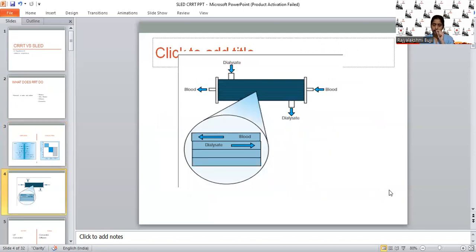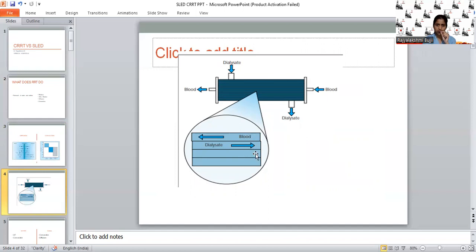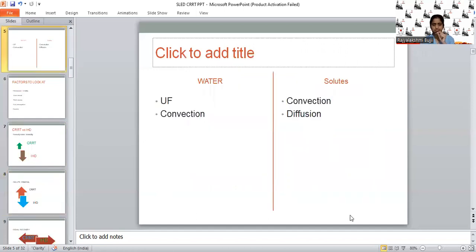In the case of intermittent hemodialysis, the diffusion process is facilitated by counter-current flow of both blood and dialysate fluid. The filter contains parallelly placed porous channels; within the channels, blood will circulate, and around the channels, dialysate fluid will circulate — but both move in opposite directions. This facilitates the concentration gradient and diffusion process. Water will get removed with the help of filtration and convection; solutes will get removed with convection and diffusion.